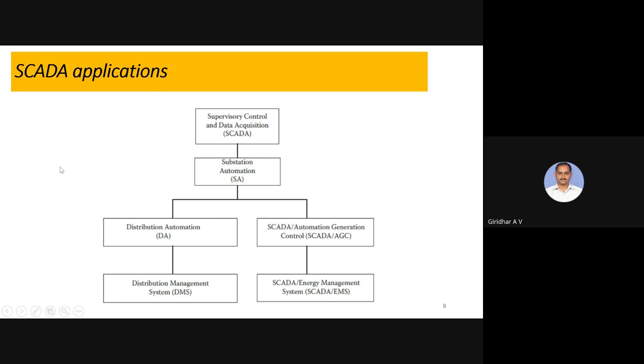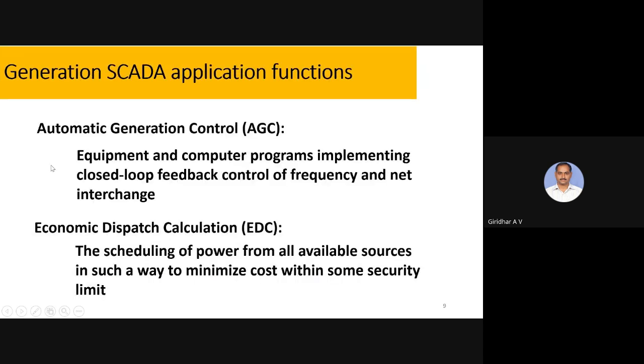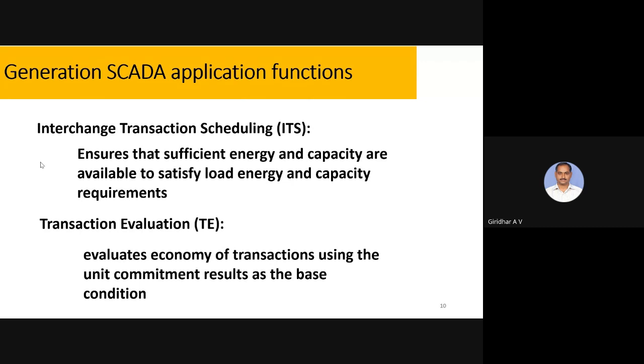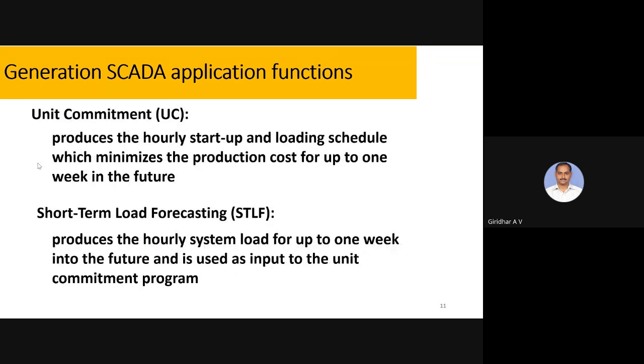From the substation automation, generation, distribution, and transmission aspects, we can see these SCADA applications. In automatic generation control, equipment and computer programs implement closed loop feedback control of frequency and net interchange with SCADA. Economic dispatch calculations can be done so that cost is minimized. Also interchange transaction scheduling, transaction evaluation, unit commitment, and hourly startup and loading schedules that minimize the production cost, and short-term load forecasting can be used.